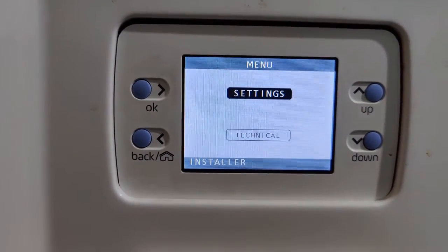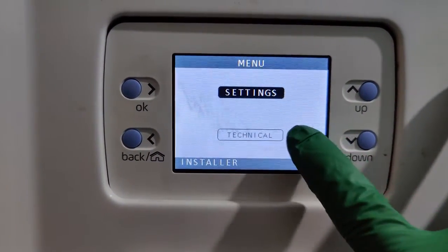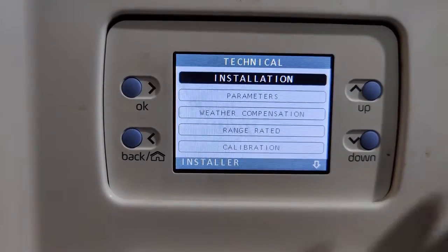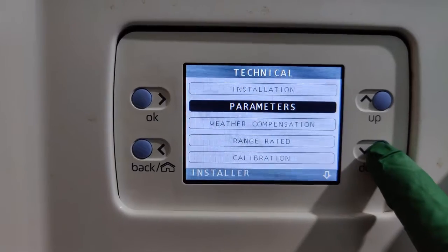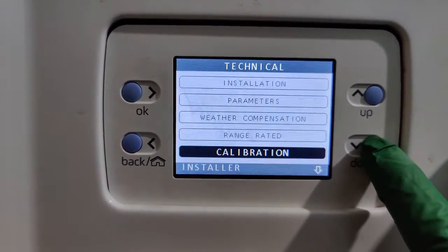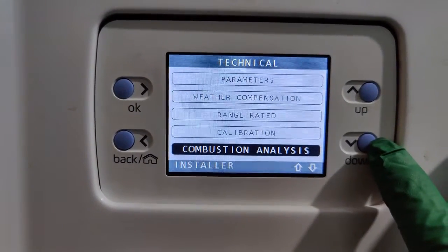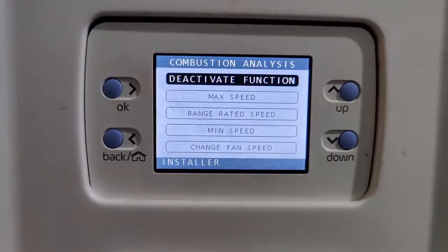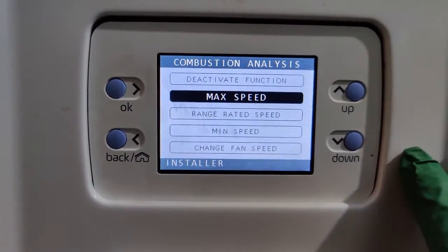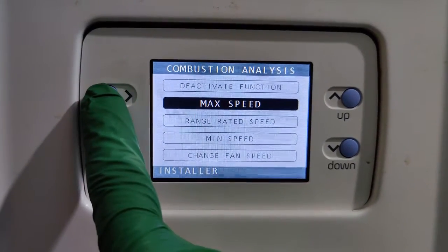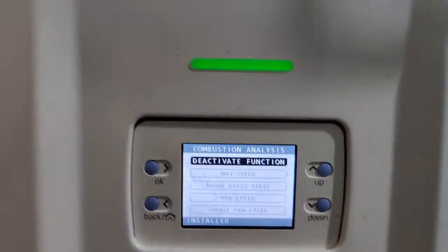OK the password and you'll now see Settings as well as Technical. Go to Technical and OK that. It has quite a few different sub-menus, but the one we need is Combustion Analysis. OK that and activate the function. We want the boiler to go on maximum speed first — that's maximum rate — then minimum speed is minimum rate. Confirm maximum speed and the boiler will fire up on maximum speed.